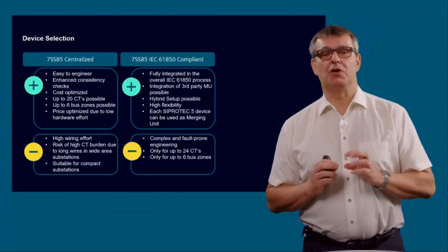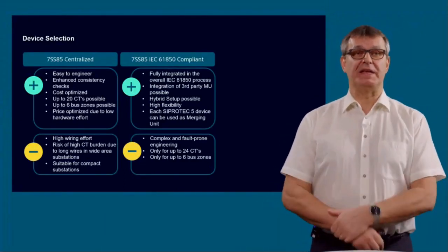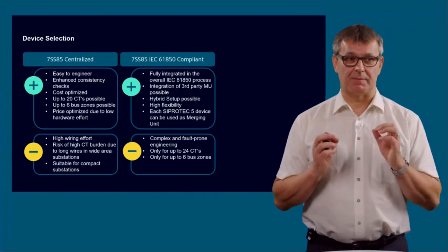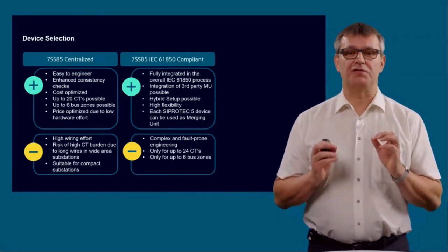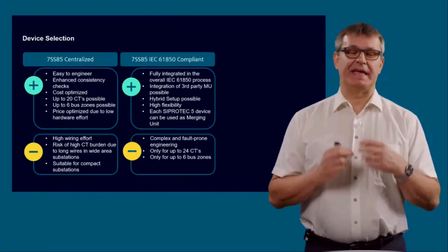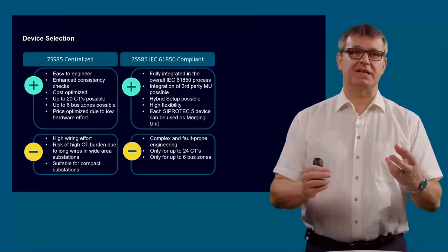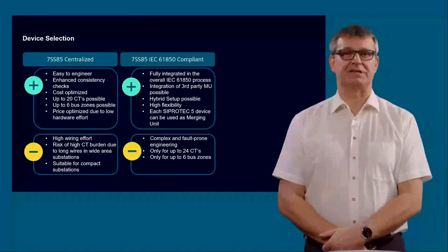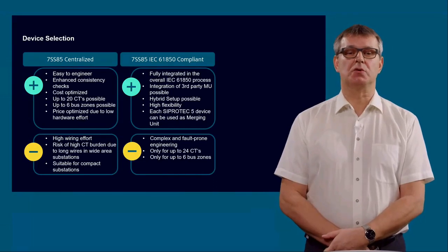The setup is only for a maximum of 24 CTs, a maximum number of 24 bays. And as we are using the same device as a centralized busbar protection, it's also limited to up to 6 busbar zones.